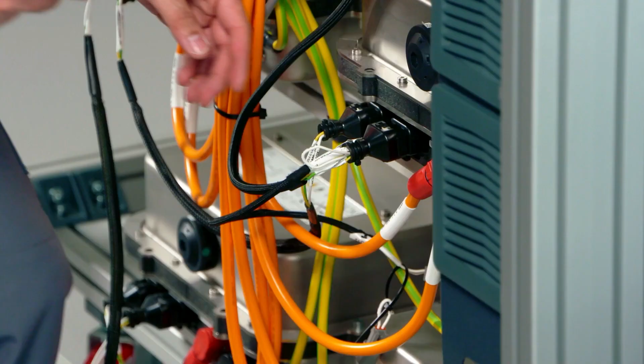The first thing is to switch off - you see the green light going off, voltage is switched off. Now we are securing against reconnection. In this case that means we take off the connector from the battery, the CAN connector, so there's no chance the battery can reconnect us with the contactors again - securing against reconnection.